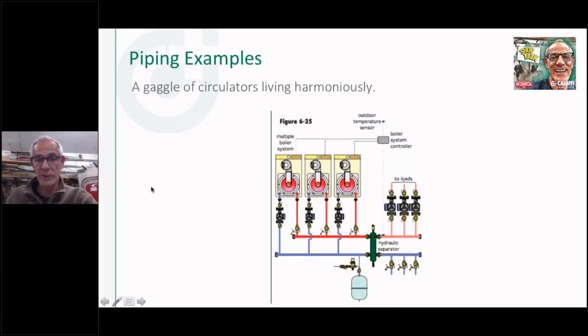And you're going to get air and dirt removal through your separator. As any air comes out of solution, as we start heating up these boilers, we're going to get more air out of solution. So this is a really nice way to pipe and to purge those systems, like putting a purge cock on the individual returns for all those loops. These would want to have check valves, of course, in them, on the distribution side of those circulators.